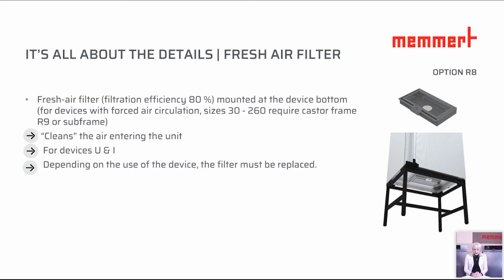Now we come to the filtration of fresh air before it's going to be entering the interior of the chamber. We have here a fresh air filter with an efficiency of 80%. This is according to the filter class G3 and is mounted at the device bottom. This is for devices with forced air circulation sizes 30 to 260, and this requires also a subframe, or the caster frame, which is the 2 parts with a height of 140 millimeter with casters. That is in order to enter clean air in the unit for devices oven and incubators, and depending on the use of the device, the filter will have to be replaced. And that is actually very easy. It's just adjusted by some screw. Yeah, let's go on to the next one.